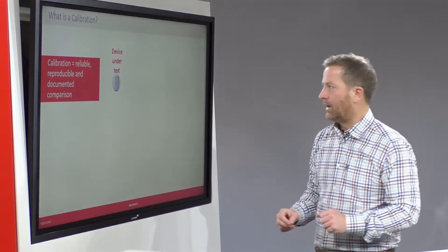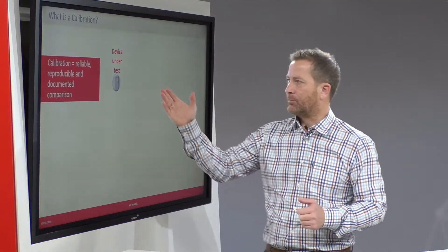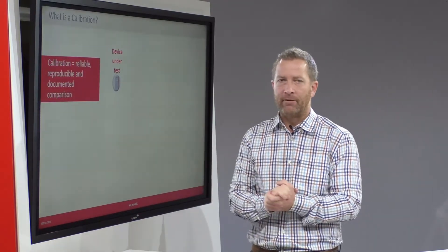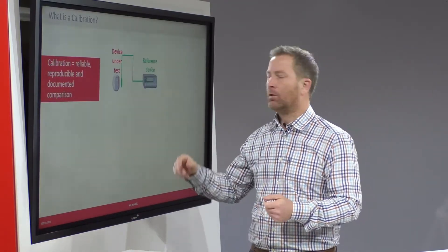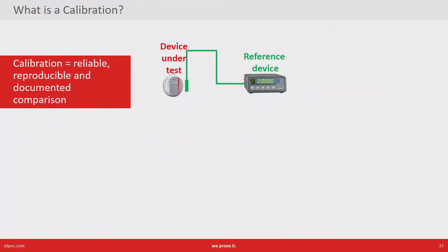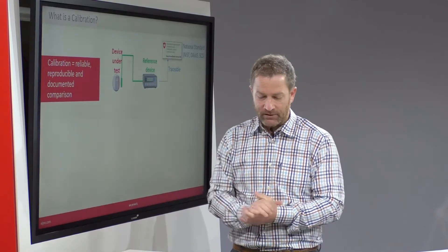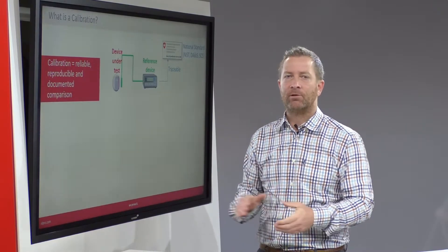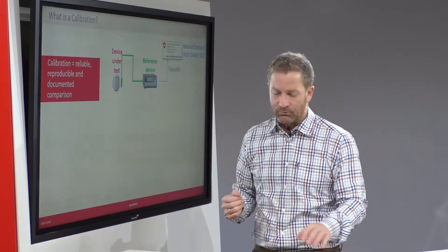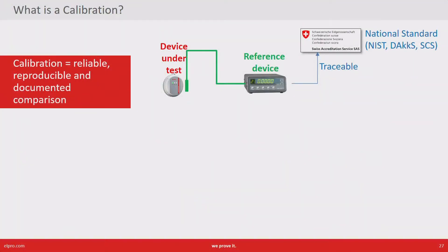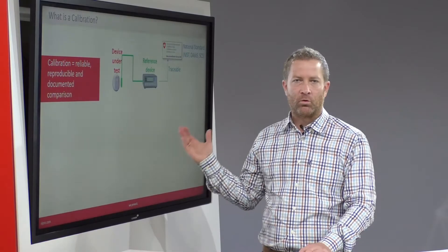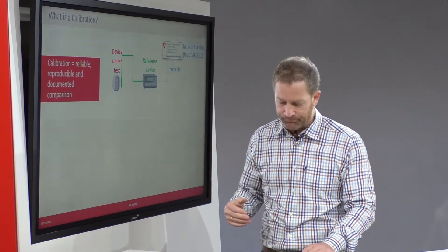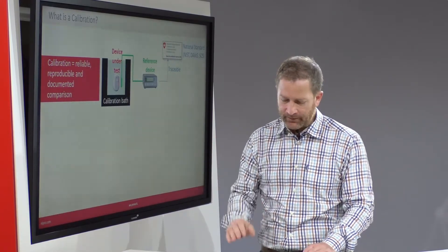These devices we now want to calibrate and produce a reliable, reproducible, and documented comparison to a reference instrument. The reference instrument is a high-precision instrument traceable to the national standard. In Switzerland this would be SAS, the Swiss Accreditation Service. In the US it's NIST, or in Germany it's DAkkS, the German Accreditation Service.